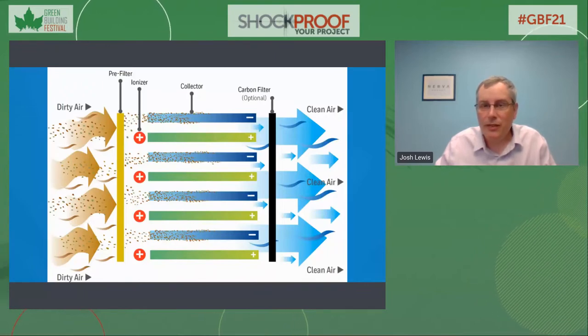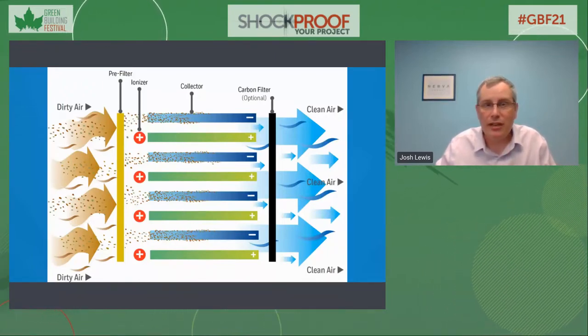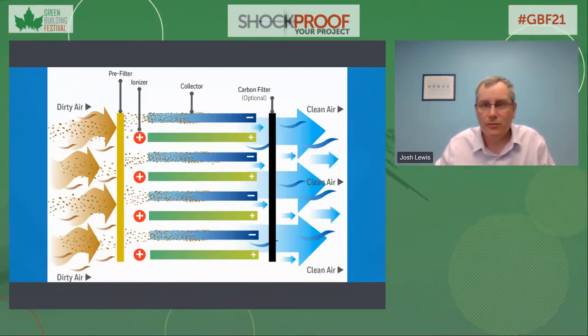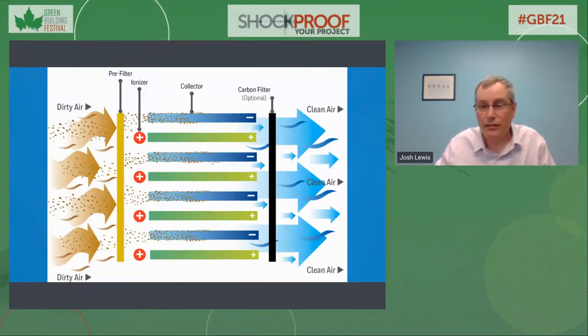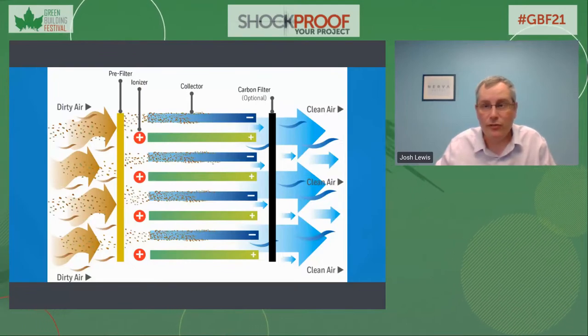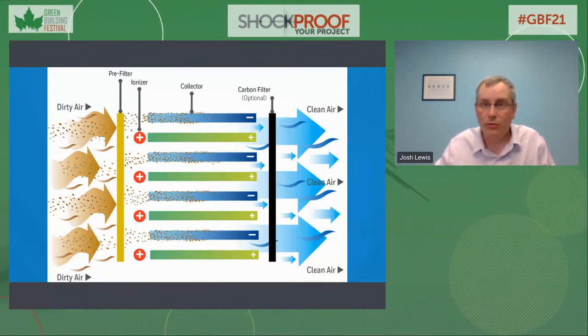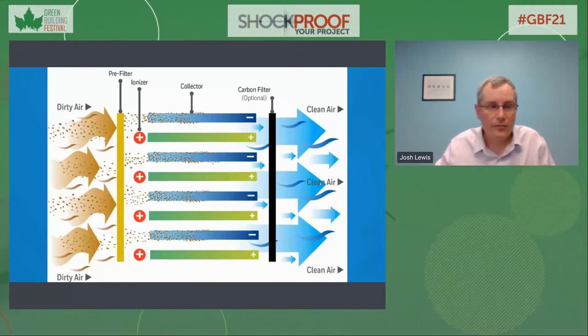While they have not typically been a standard in HVAC systems, many off-the-shelf retrofit kits are available. However, if considering going this direction, the whole picture must be evaluated, including the fact that monthly washing of the filters will be needed, a HEPA level performance will likely not be achieved, and some electrostatic filters can generate ozone as a byproduct, which is an indoor air pollutant that is not desired.